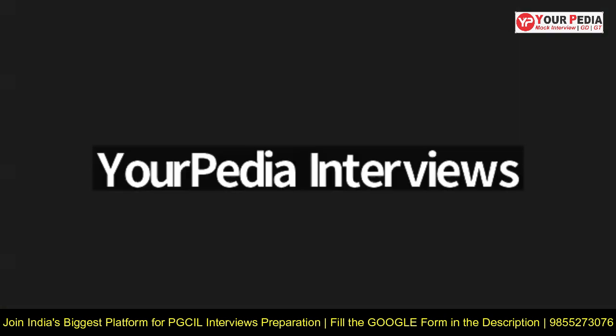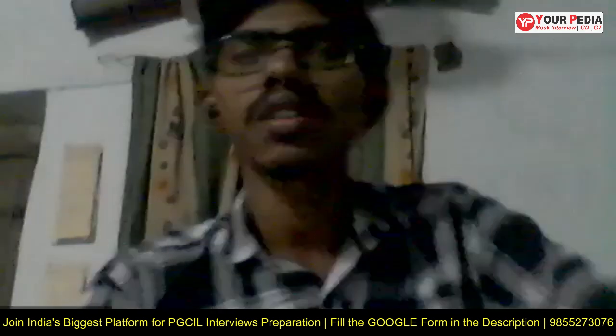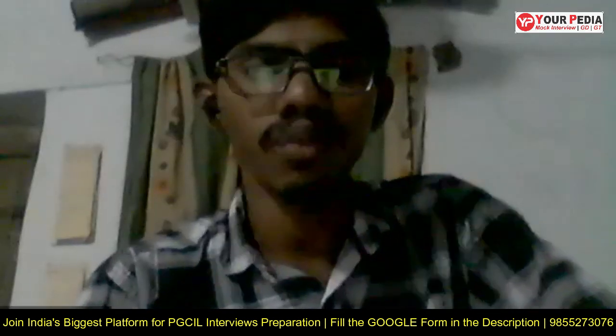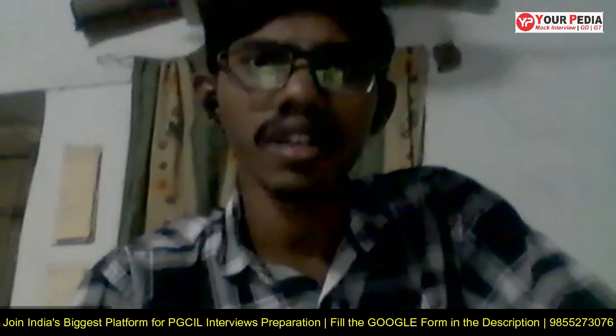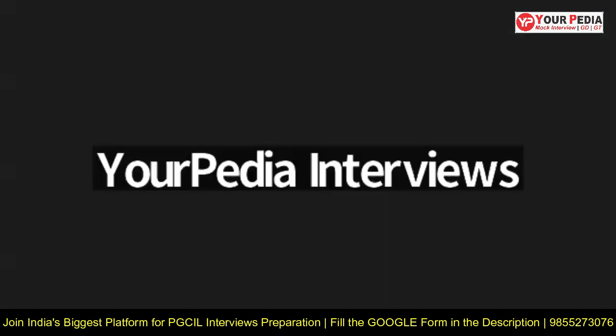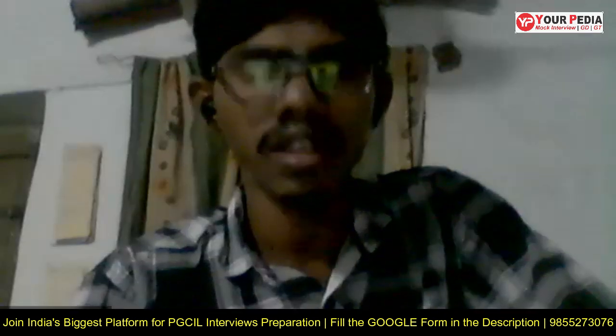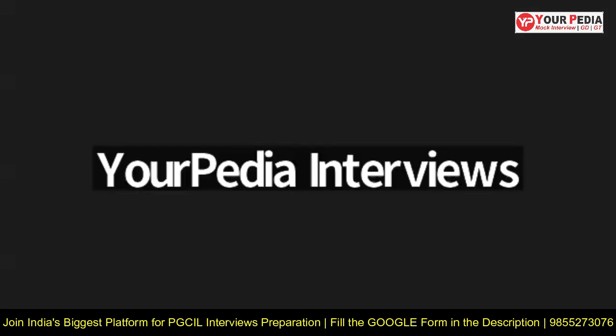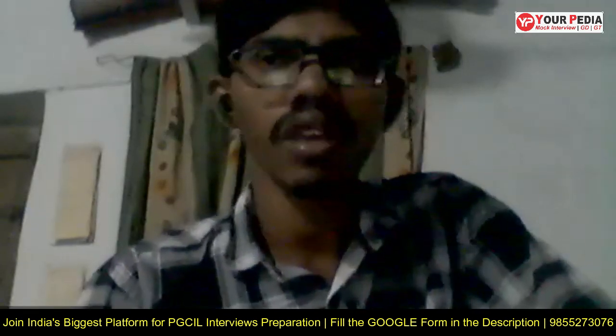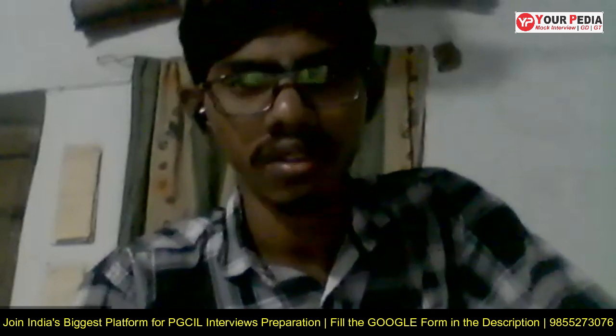Okay. Do you think that the symmetrical fault really exists or it's purely imaginary? Sir, sometimes it will exist, sir. For example, generally the most frequently occurring fault is the LG fault, sir. But in that case, our system is not grounded well. Then we have a chance of getting an arcing ground, sir. At that time, that LG fault converts into a triple L fault, sir.